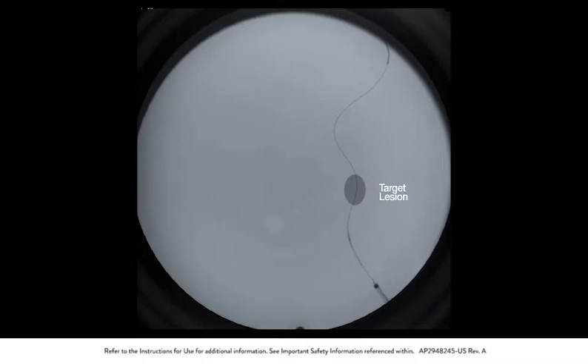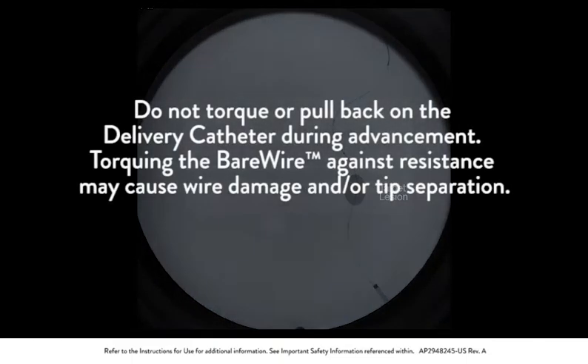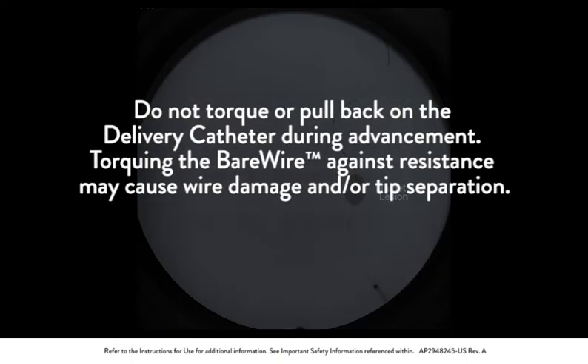Carefully advance the delivery catheter over the bare wire to the intended filtration element deployment site. Do not torque or pull back on the delivery catheter during advancement. Torquing the bare wire against resistance may cause wire damage and or tip separation.